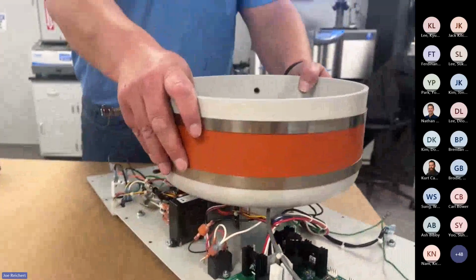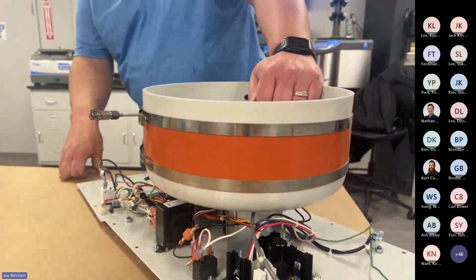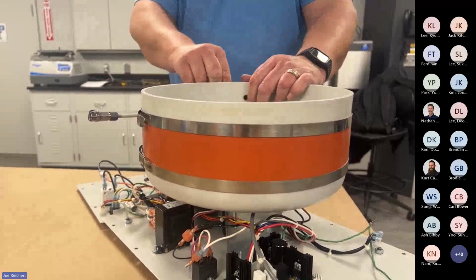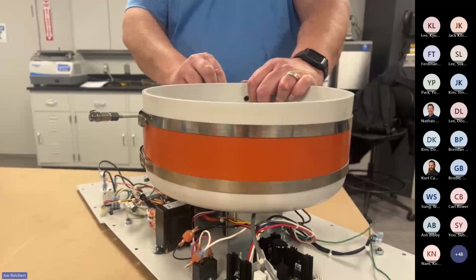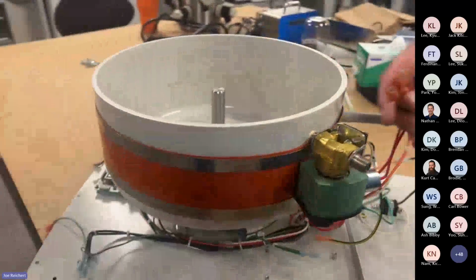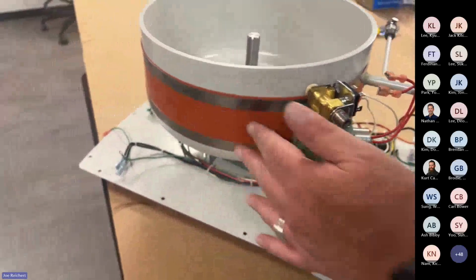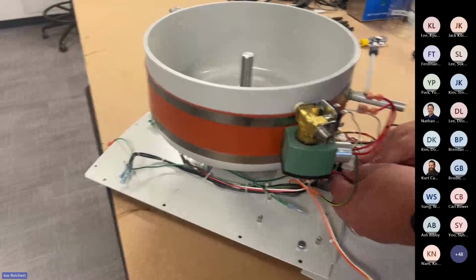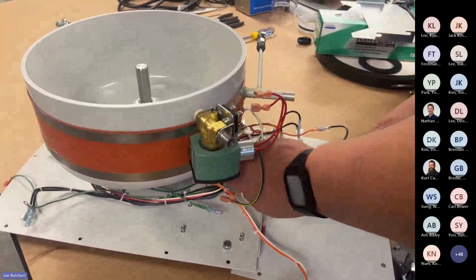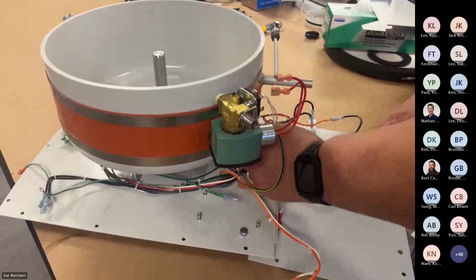Now we're down to the whole chamber, and we need to start removing it, but we can also remove some of the wires connecting here as well. This is a little bit of an older system, so it has some wires onto its vacuum release valve here. So I'm just going to remove these from the vacuum release valve. This is a band heater on this unit, so it has an extra, it's for preheat, but it comes on to make it faster for heating. We'll remove these wires from the relay.